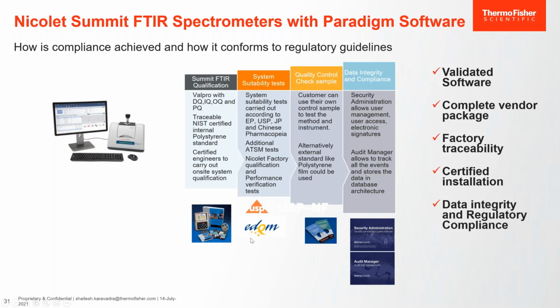The use of a quality control check sample really depends on the customer and on what test they do. For example, if they are doing an identity test, they make sure that they run a quality control sample after the performance qualification to make sure that the ID test is okay. Alternatively, external standards like polystyrenes are widely used to establish the performance qualification before any real measurements are done on a system.